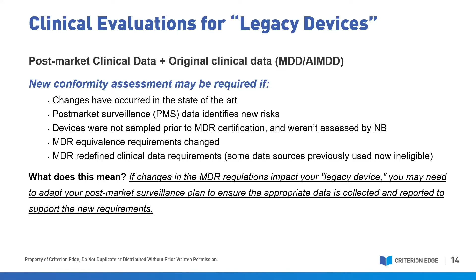If post-market surveillance data has identified new risks, if the device was maybe not sampled during MDD certification prior to MDR certification, and therefore was not assessed by a notified body, maybe MDR equivalence requirements have changed for your device, or maybe the MDR has redefined clinical data requirements and some of the data sources that you used previously for MDD or AIMDD are now ineligible. In other words, if changes in these MDR regulations impact your legacy device, you may need to adapt your post-market surveillance plan to ensure that the appropriate data is collected and reported to support these new requirements and maybe the changes in the state of the art that affect your device. This will be used in conjunction with the data that you previously submitted under MDD or AIMDD.